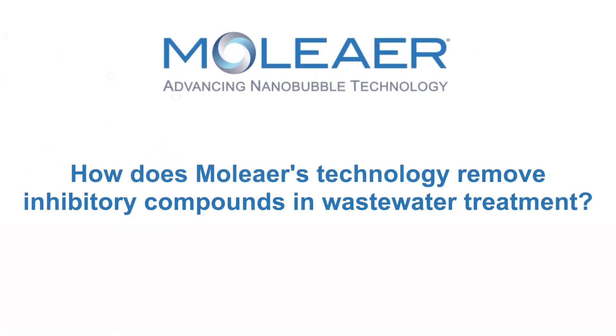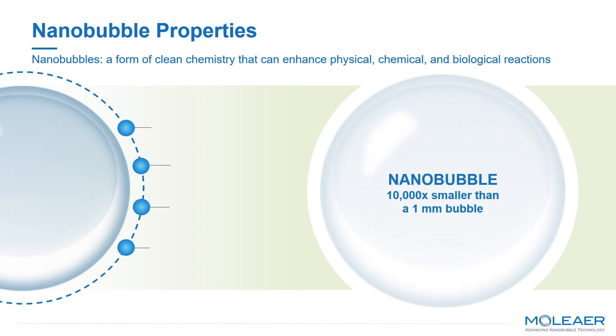How does Moleaer's technology remove inhibitory compounds in wastewater treatment? Moleaer's technology generates a form of clean chemistry using nanobubbles, which have unique properties due to their size. Nanobubbles are roughly 100 nanometers in diameter — 10,000 times smaller than 1 millimeter fine bubbles that you would get from floor-mounted diffusers.